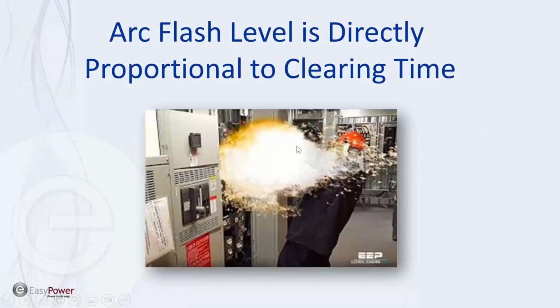So we have to know how far out this ball of fire is going to go, and that ball of fire is going to be directly proportional to the clearing time of the protective device, depending on what that is. And of course, the level, the heat and pressure also have an impact. The available fault current has an impact on that.